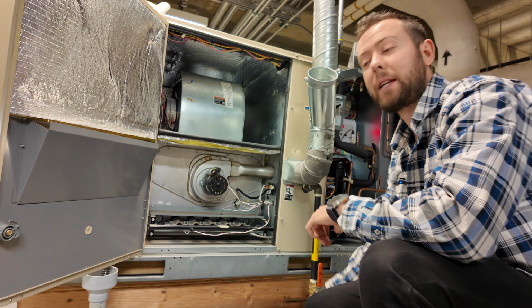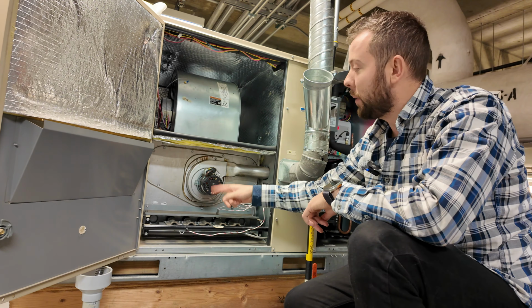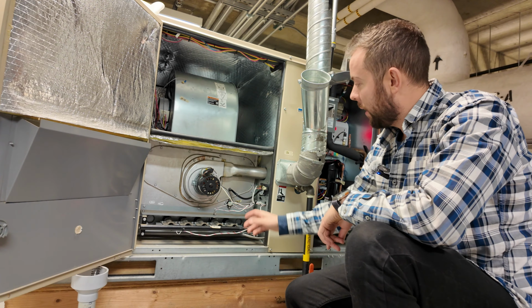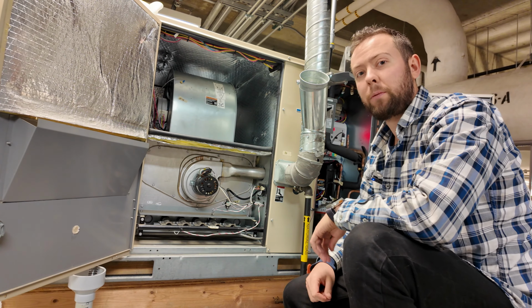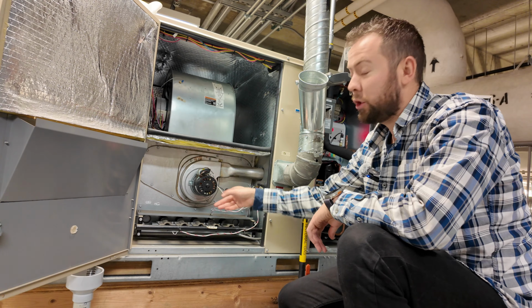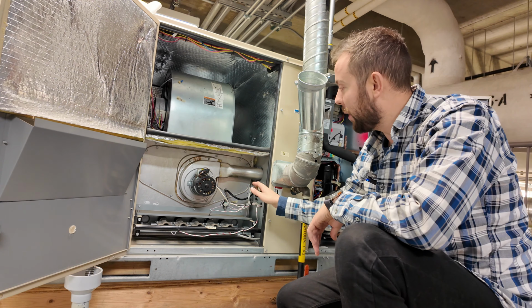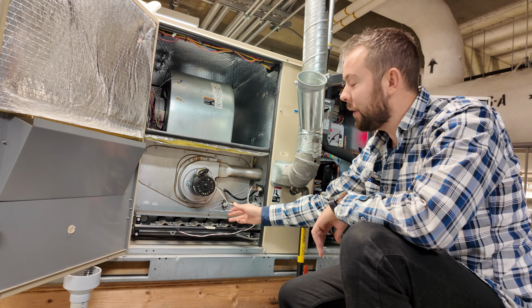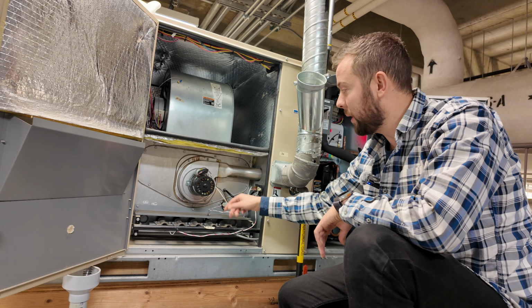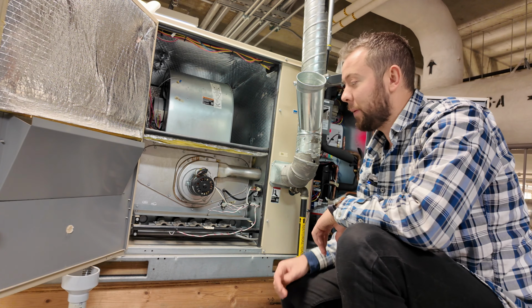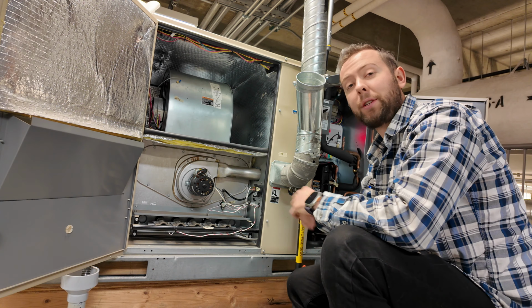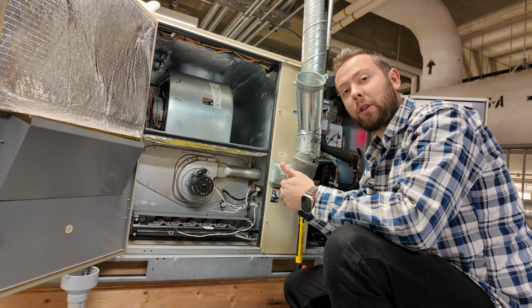Once the thermostat closes for heating, combustion motor spins up. It will then close the pressure switch. It will induce a draft, closing the pressure switch. Then voltage will flow through the rollout switch, high limit, and we have another high limit. If it says all the safeties are good, it's going to go into its heating cycle.